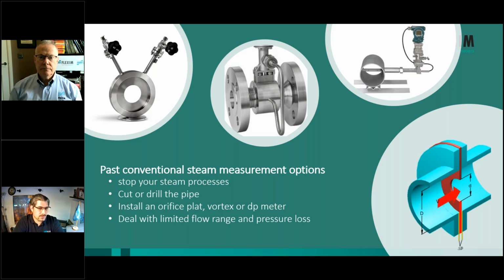You want to reduce your steam flow, so at one point you will achieve that, but then you have a meter installed that would not be able to detect those low steam flows anymore. Or even from the beginning, you will have problems metering your steam flow when you are on low demand, like in this time period right now. It is still warm enough that you do not need much heating, and still cool enough that you do not need much air conditioning. So steam demand would be quite low.